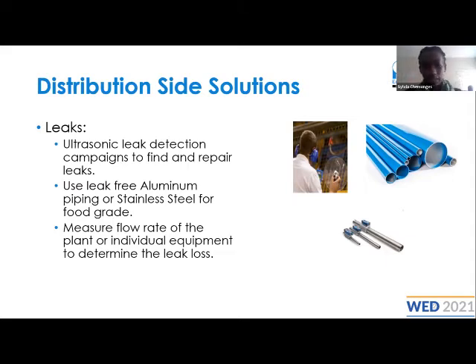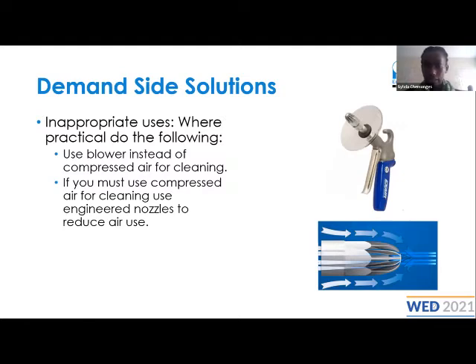Then the next thing to consider is measuring flow rates to individual machines. Then from there, you can determine if there are any losses to these particular machines. Okay. From there, we go to the demand side. On the demand side, we noticed that we had challenges in terms of inappropriate use, artificial demand. And so how exactly do we fix these problems? For inappropriate use, maybe it would be best to try and, first of all, educate people who work within your company. And from there, figure out ways in which you can minimize your compressed air use.